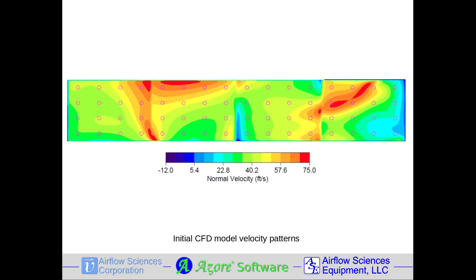This figure provides CFD results for the vertical velocity component at the plane immediately upstream of the tube bank. In this plan view, side-to-side stratification is evident, with higher velocities on the right side of the unit due to the gas turbine profile. The flow uniformity, expressed as velocity RMS or coefficient of variation, has a value of 28%. Uniform flow is typically considered under 15% RMS.